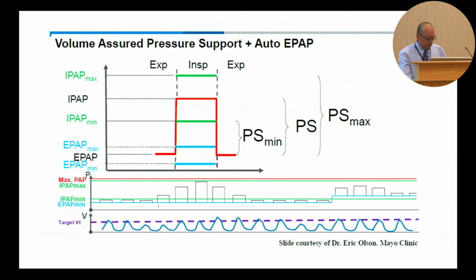So it's a very automatic mode that has many advantages depending on the sleep position. You can imagine that when the patient is sleeping on the side, they probably need less IPAP. When the patient is in REM, they probably need more EPAP and IPAP. And you basically have both parts adjusted automatically, and that's what many patients would need. Now, as of now, it's not clear if AVAPS is better than BiPAP ST, but you can see that there are advantages with automatic adjustment of pressures.